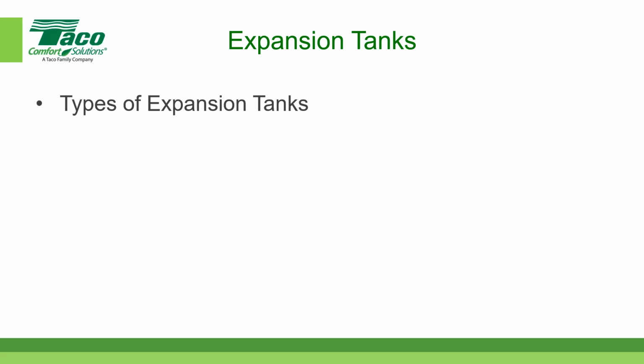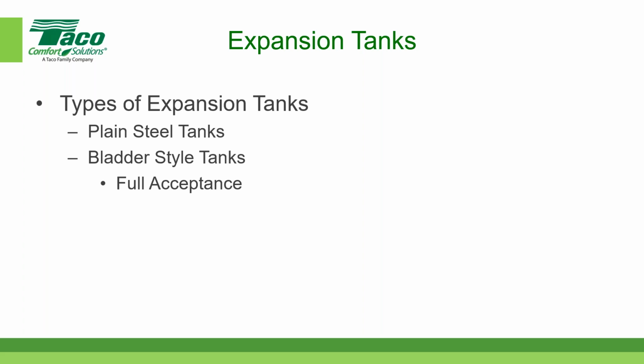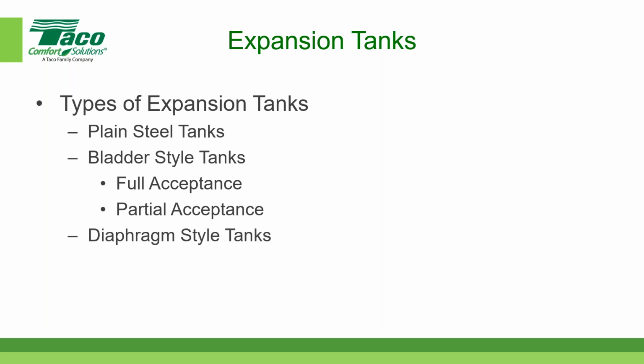The types of expansion tanks we typically see today include plain steel tanks, the first major category. A second category is called bladder style tanks, which has two subcategories: full acceptance and partial acceptance. The last category is called a diaphragm style expansion tank, typically known as partial acceptance tanks. So that's 3 major categories, and under bladder style tanks, 2 subcategories - 4 different styles of expansion tanks total.